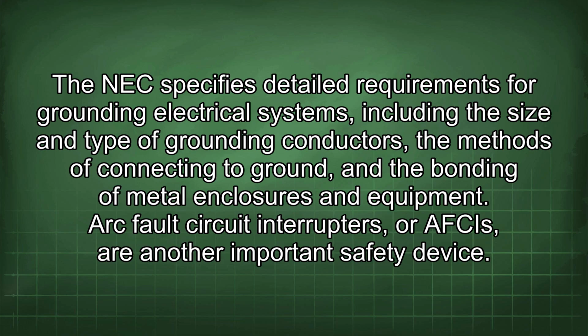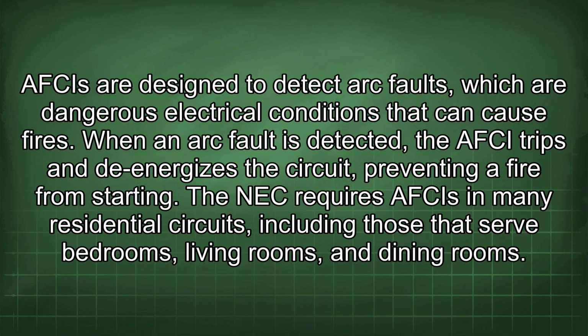Arc fault circuit interrupters, or AFCIs, are another important safety device. AFCIs are designed to detect arc faults, which are dangerous electrical conditions that can cause fires. When an arc fault is detected, the AFCI trips and de-energizes the circuit, preventing a fire from starting. The NEC requires AFCIs in many residential circuits, including those that serve bedrooms, living rooms, and dining rooms.